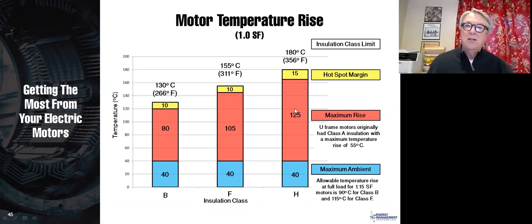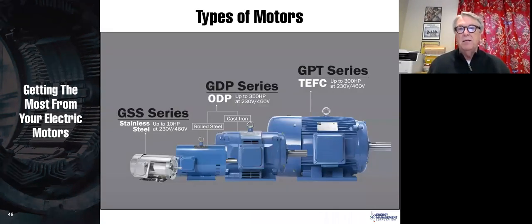This is Class H. Class H gives you 180 degrees, and it is good for 125 degree rise or 180 degrees. And notice that NEMA gives you a 15 degree hot spot there, which means that they expect someplace in that motor to be running 15 degrees hotter than the average if you use that. So again, I'm going to talk about this some more, but if we want a really stout motor, we want to make sure that we use Class F insulation with a Class B rise.